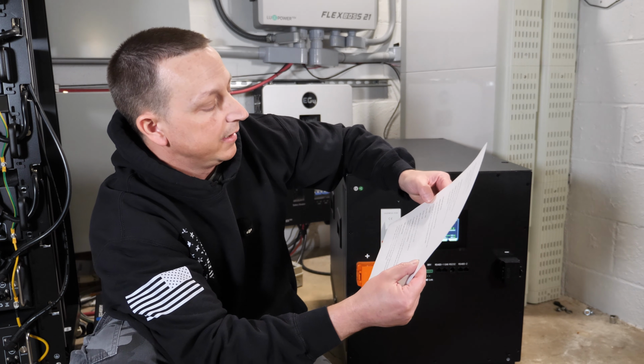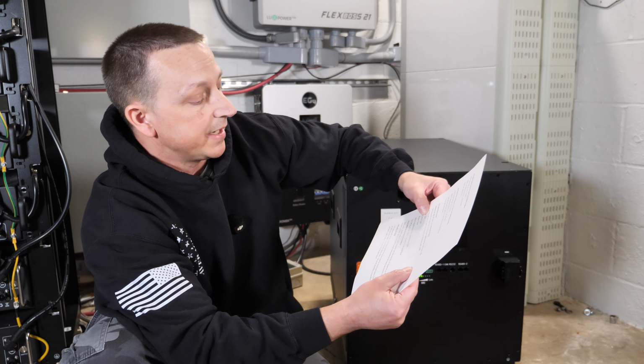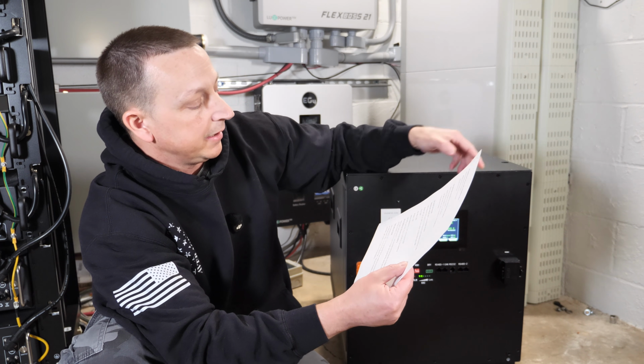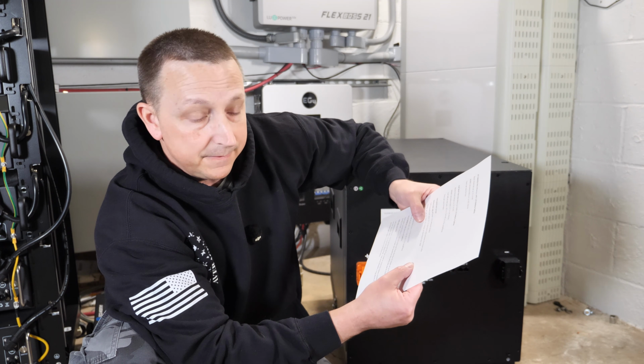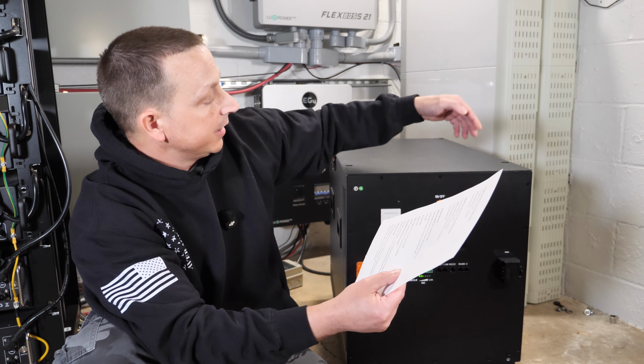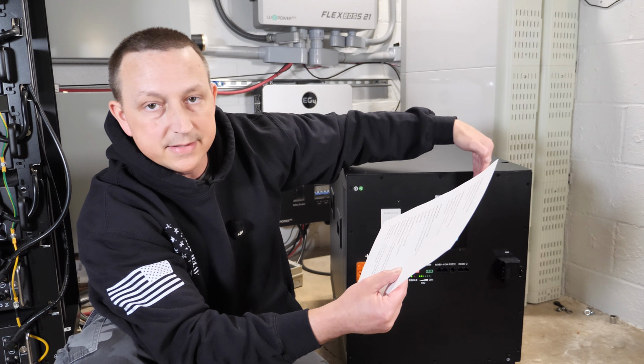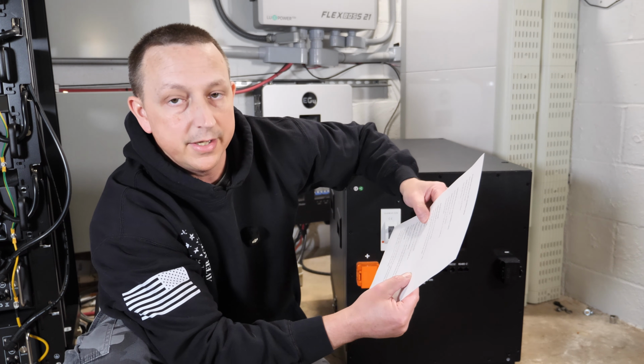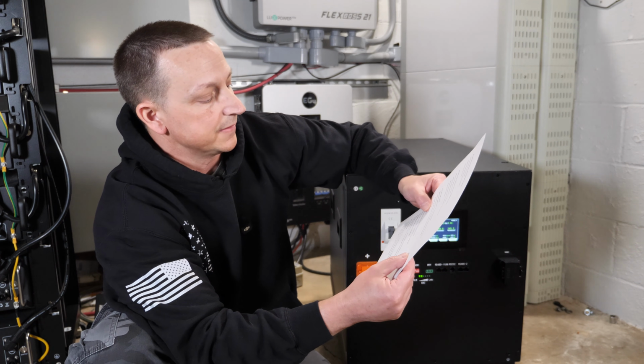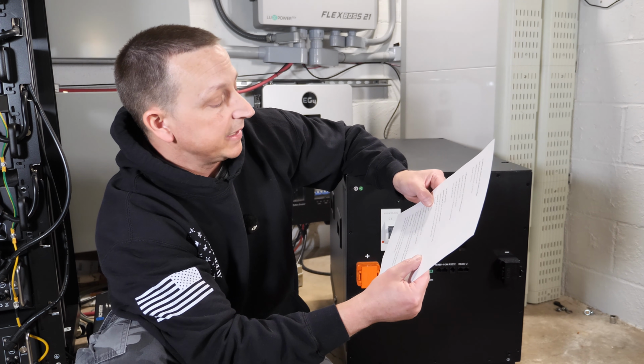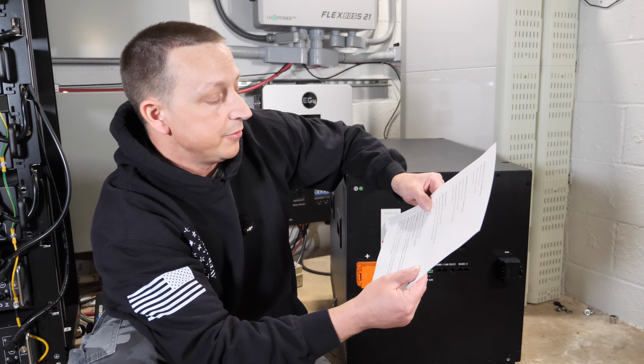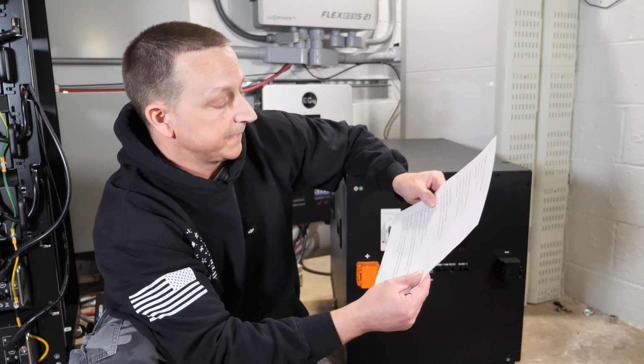The bus bar right off of cell number 16 was 150 degrees Fahrenheit, and just a little lower where the bends were, it was 166 degrees Fahrenheit. The fuse was going to be the hottest, and we got around 236 degrees Fahrenheit.